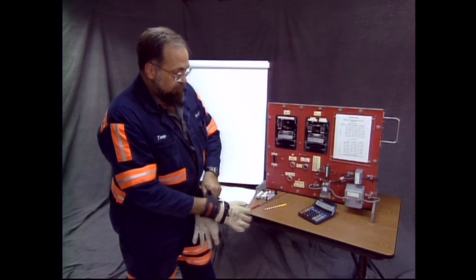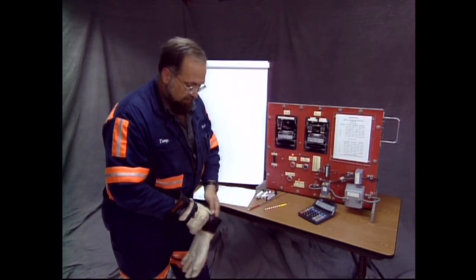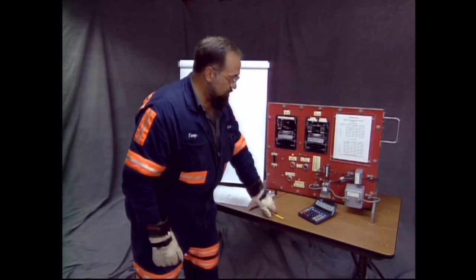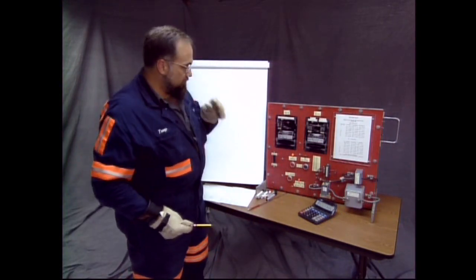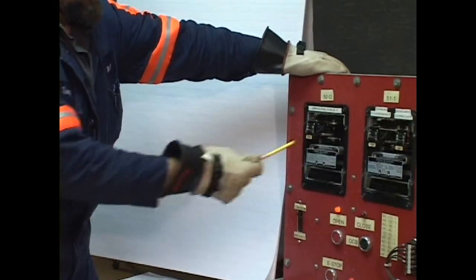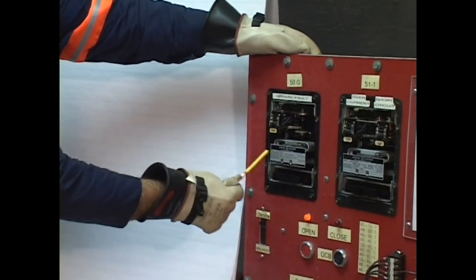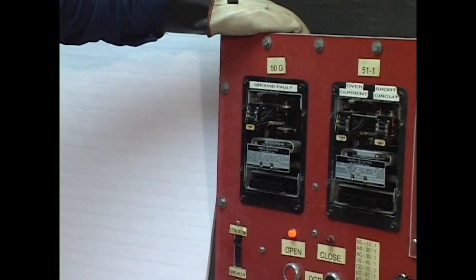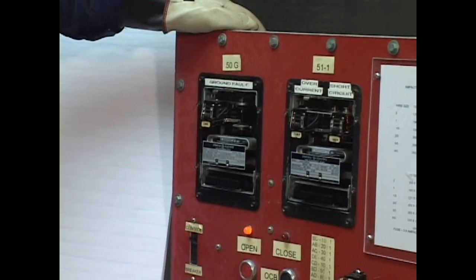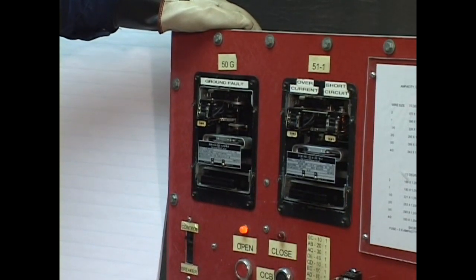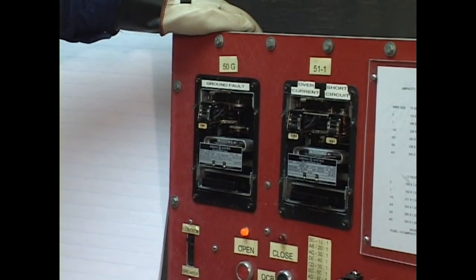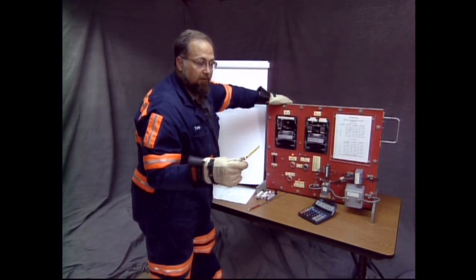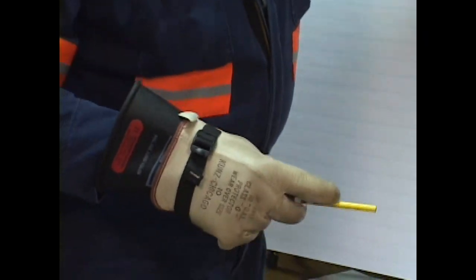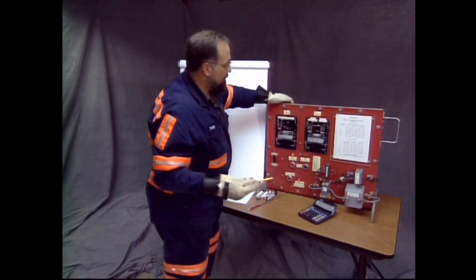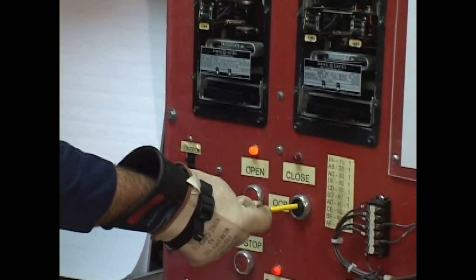Now we're going to do manual operation of these devices. Now this, as well as the ones that you check in real life, as part of your job, has control voltage on these relays. And there's a lot of this relay here that is energized with control voltages, with 110 volts or 120 volts. So we're going to use a non-conductive rod here. This is just a pencil. And wear our low and medium voltage gloves for safety, and do a manual operation. Now, we're going to close the OCB.